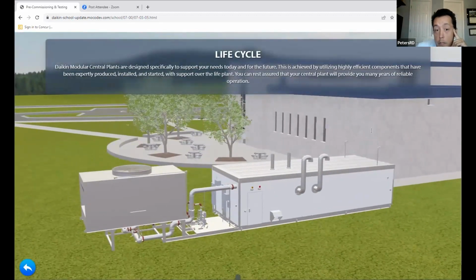In terms of life cycle, a water-cooled Daikin system like this will last longer than other systems. Often we focus on first costs, but if you're giving the owner the best solution, you think about how long it will last—will they want to rip it out in 10 to 15 years? A system like this, built and certified by Daikin, AHRI rates at about 22 years for water-cooled systems, but I've seen water-cooled systems running 40 to 50 years, as long as they're maintained properly.